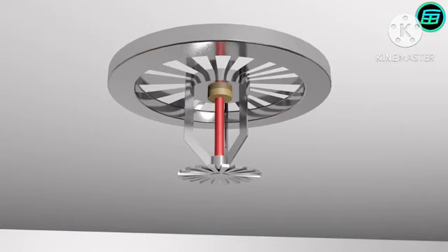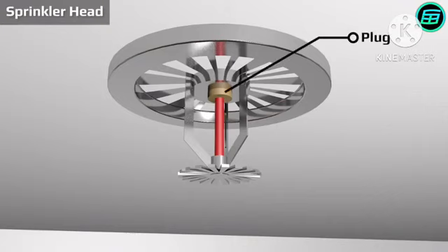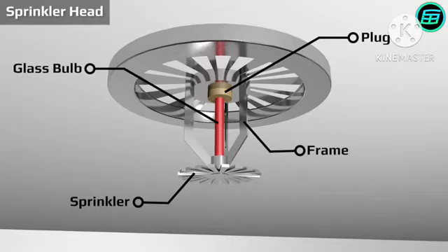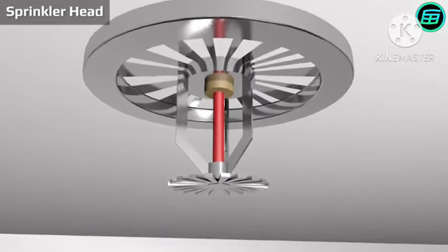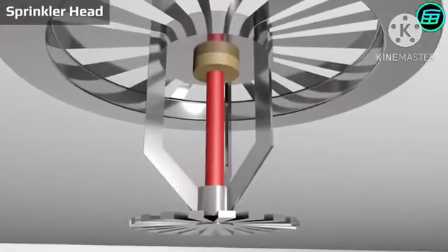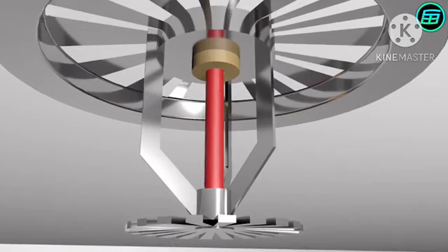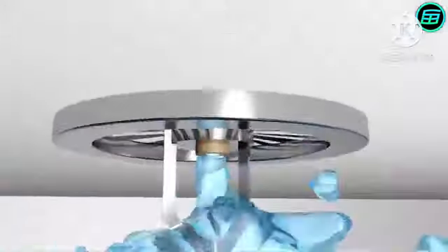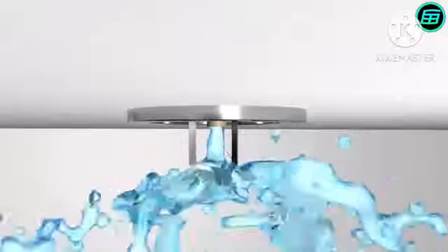The essential components are a water supply system and a fire sprinkler head. The sprinkler head is made up of a plug, a liquid-filled glass bulb, a sprinkler and a frame. When a fire starts, the temperature of the environment rises and the liquid in the glass bulb begins to expand. If the temperature continues to rise, the liquid expands so much that it breaks the glass. There's then nothing left to stop the water and it begins to come out from the plug. When water hits the sprinkler, it's spread over a larger area.